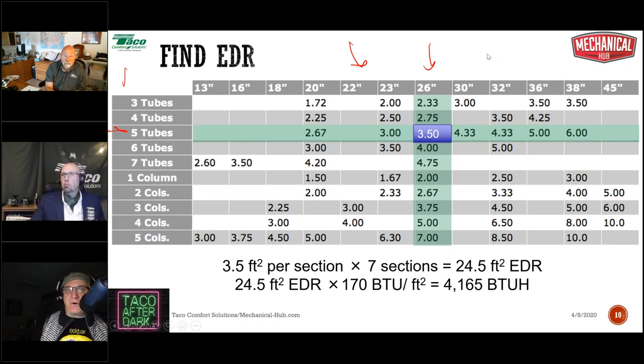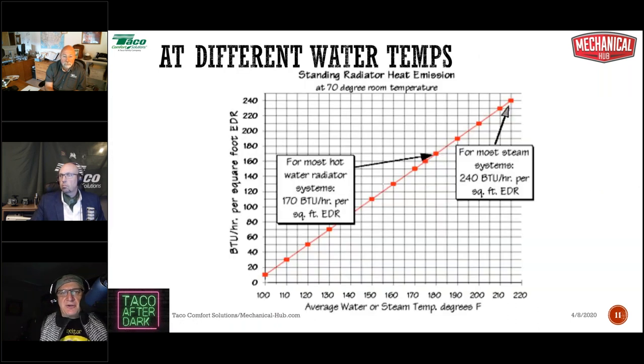Now, that's at a specific water temperature. Let's take a look at how water temperature affects the output of a cast iron radiator. We found this chart online, and it's standard. Now, if you were to look at a steam radiator, with boiling water, steam basically, we get about 240 BTUs per hour per square foot of EDR. The 170 number comes down from here at 180 degrees. Now, we're talking about water temperatures here.